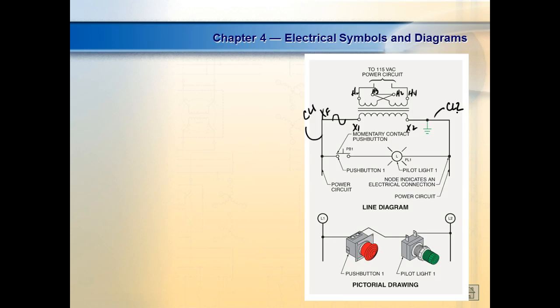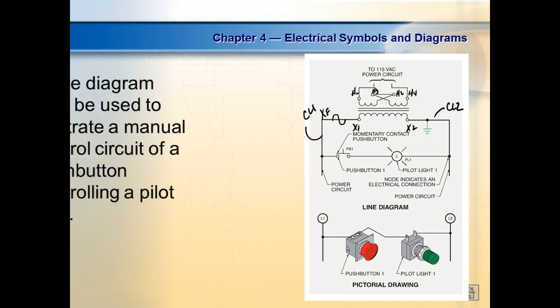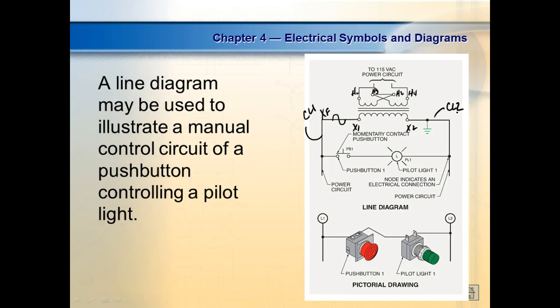This would be a very simple circuit. Normally your control devices are going to be between L1 and the load, and then your load is going to be connected to L2, unless it's what we call a magnetic motor station. It's going to have overload. So the only thing that's allowed on the L2 side is overload. We talked about that a little bit in the other class.